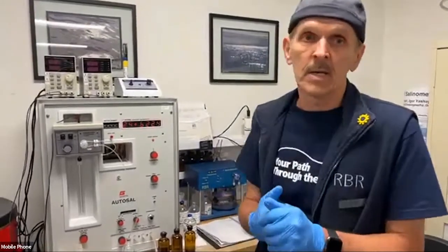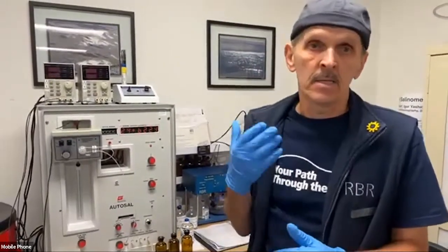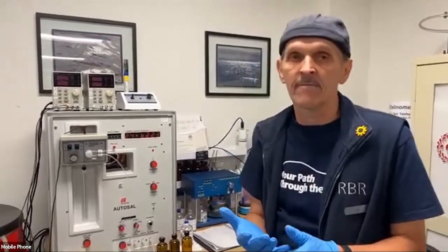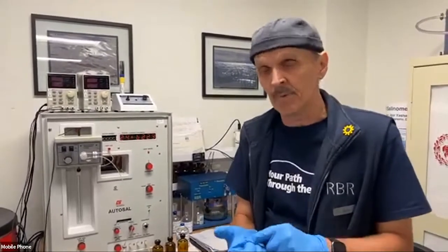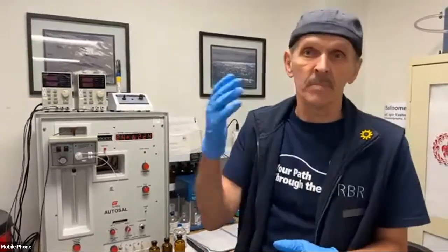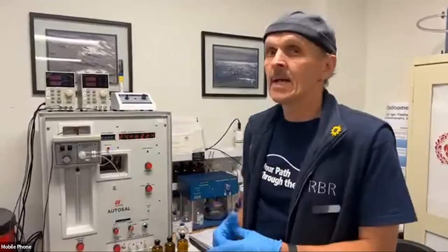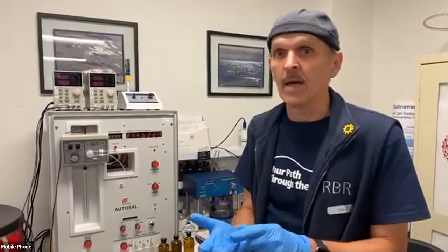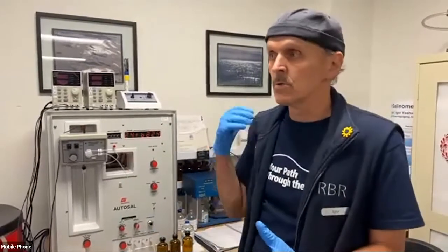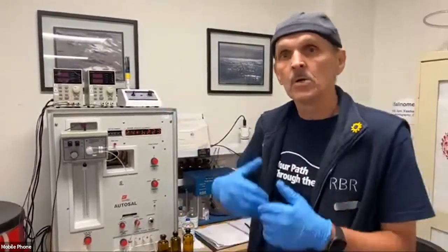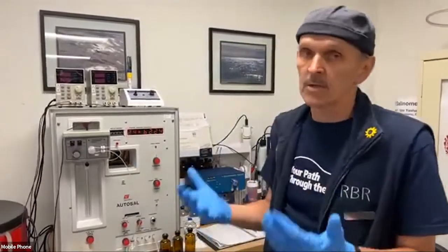But when we're talking about conductivity calibration, we need to understand that practical salinity is a derived parameter. Practical salinity, according to the practical salinity scale, is derived from conductivity, temperature, and pressure. This is why, as we move through each stage of calibration, from temperature to pressure, and now to conductivity, we know that our instrument is calibrated for temperature and pressure, and we use that data to convert salinity data from samples to conductivity data as our reference for conductivity calibration.